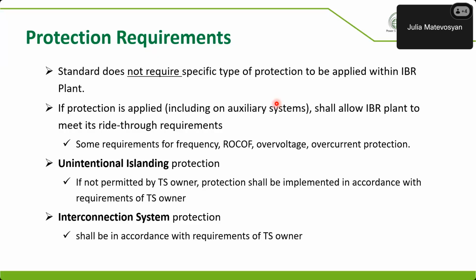Most OEMs may have their own ways of detecting an island that is built into inverters and tripping for it. Now, some entities may rely on built-in protection within the inverters, whereas others prefer a transfer-trip-based anti-islanding protection, where they have a little more control over it. So we just say, if the transmission owner requires anti-islanding protection, then implement it according to the requirements of the transmission owner, right? And then interconnection protection: we were not going to spell out how the tie line is going to get protected. Some tie lines could be short, some could be long, some prefer differential, others prefer distance. The list can be very long. So again, we simply say that any interconnection system protection should just follow the specific requirements of the transmission owner.